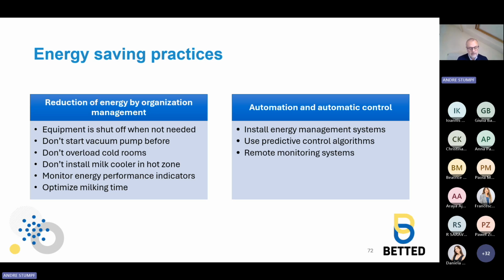according to needs. Install energy management systems that optimize the use of cold according to peak and off-peak consumption times. Use predictive control algorithms to automatically adjust parameters based on external conditions and heat load. So the installation of remote monitoring systems makes it possible to monitor the performance of refrigeration systems in real time. These tools make it possible to anticipate breakdowns, quickly identify malfunctions, and maximize energy efficiency.